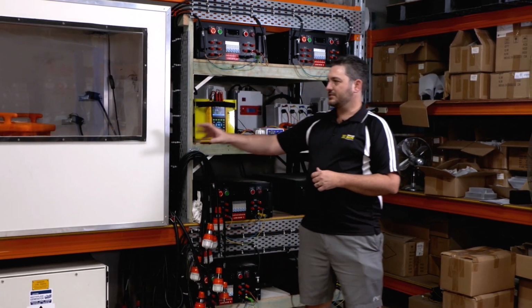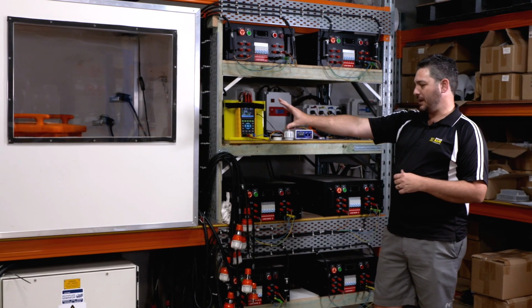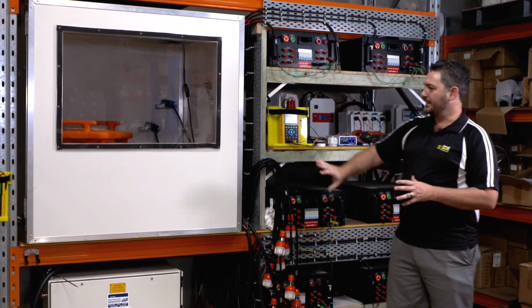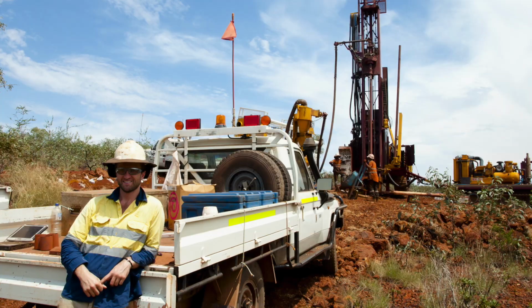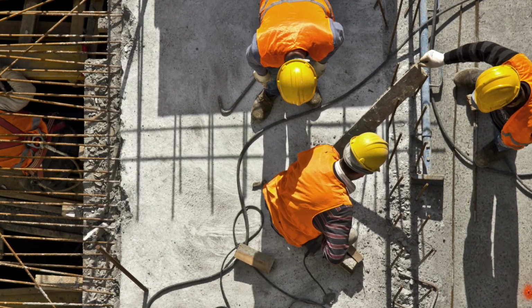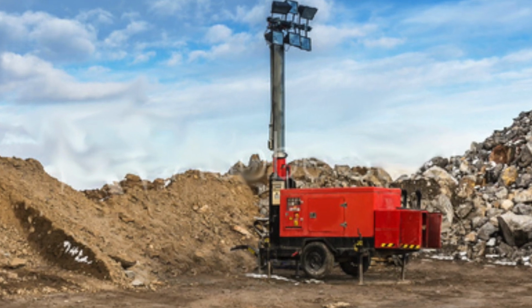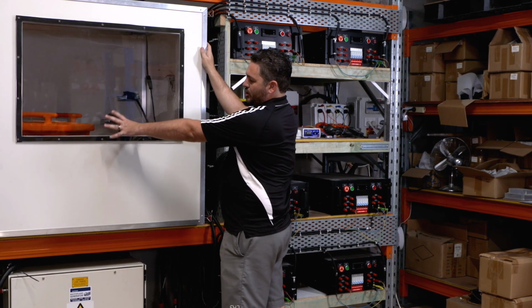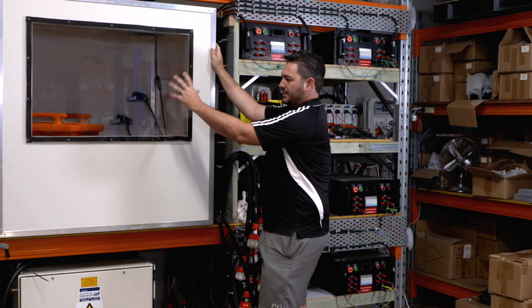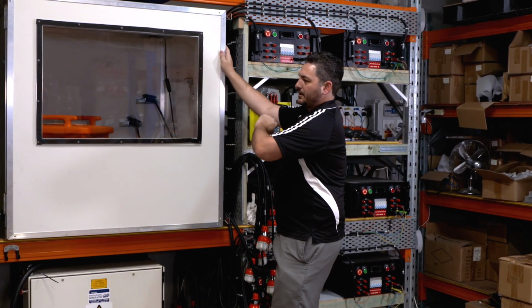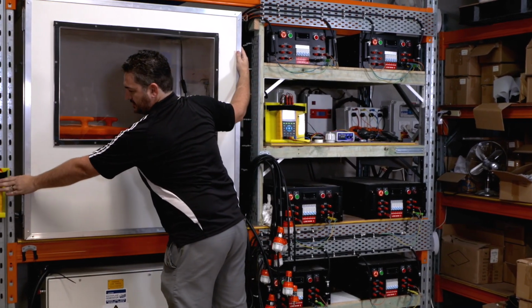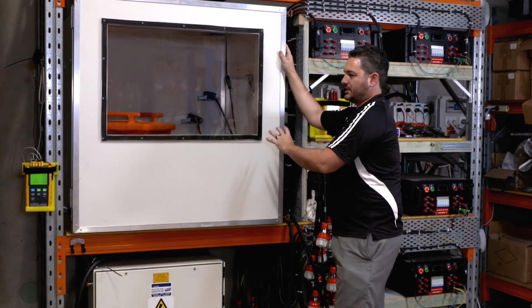So what we've got here is our thermal testing chamber. What we do here is we heat this chamber to 40 degrees to mimic outside, out west, on a mine site, on a construction site, copping sunlight, those sort of things. We've got probes set up on the RCDs, MCBs, internal wiring, all recorded here. So this records all your temperatures throughout the whole test.